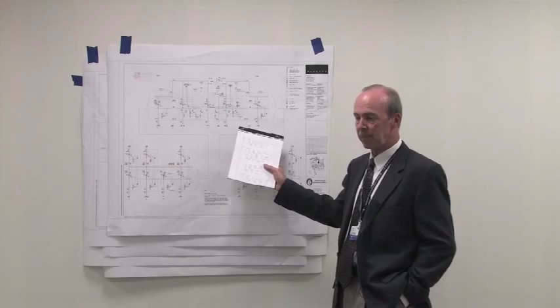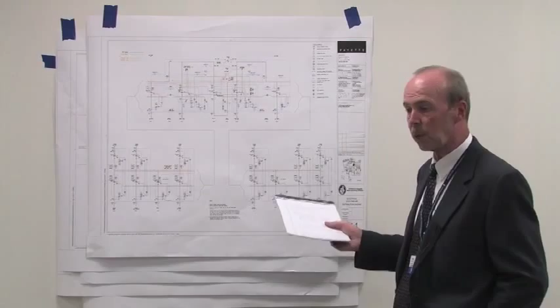So these are the original two 13.8 lines that you had before. It's a main-tie-main configuration. Both lines are on at all times. The tie is in a closed position, so you're never going to see a blip if they ever switch and take one line down.